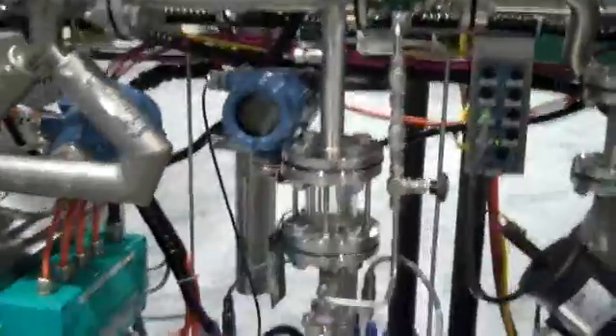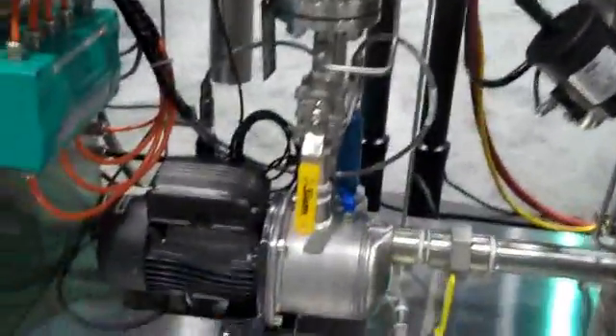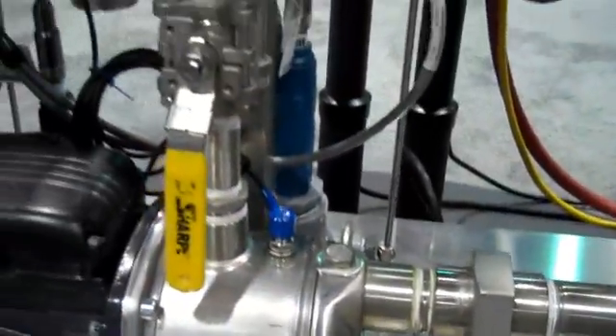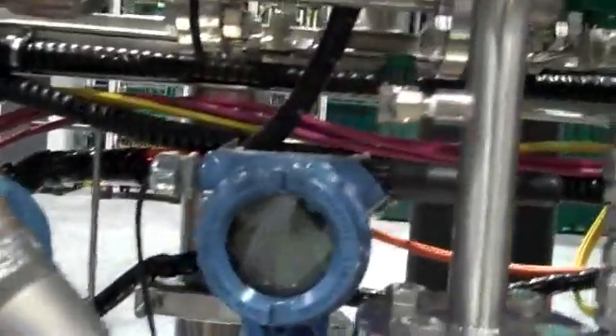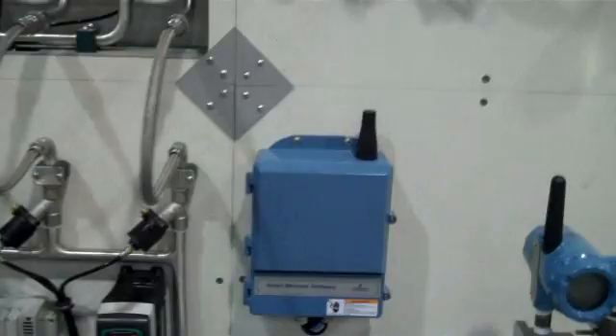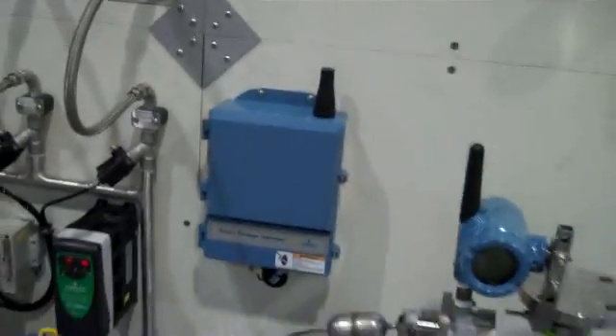Down here we also have a mix of wireless devices. Off of my pump motor combination what you'll see tucked in the corner here is a little vibration monitor or vibration sensor that's connected to this vibration transmitter right here, that little blue can. And all that feeds back to my wireless gateway which is over here on this panel. And we have a number of other wireless HART devices connected in my wireless network.